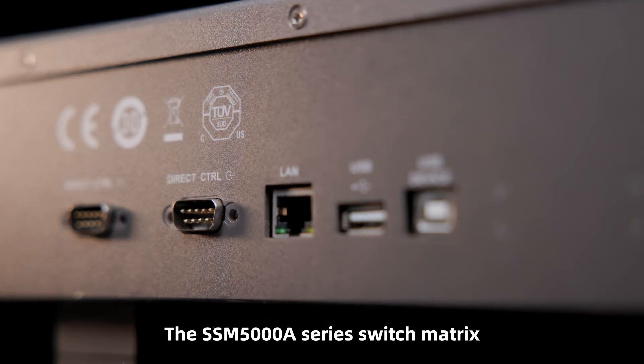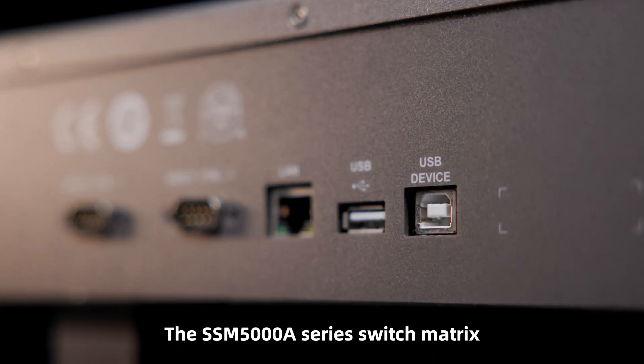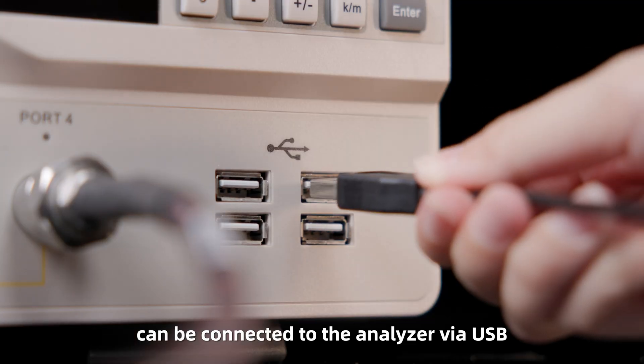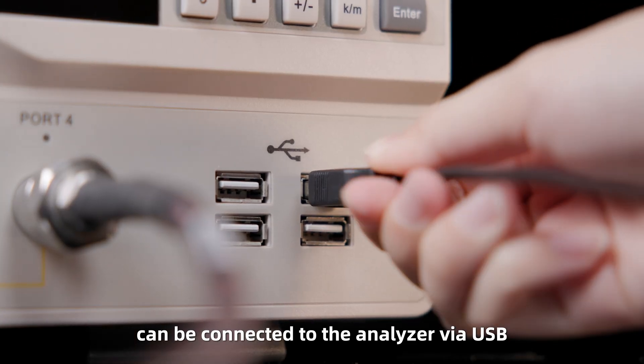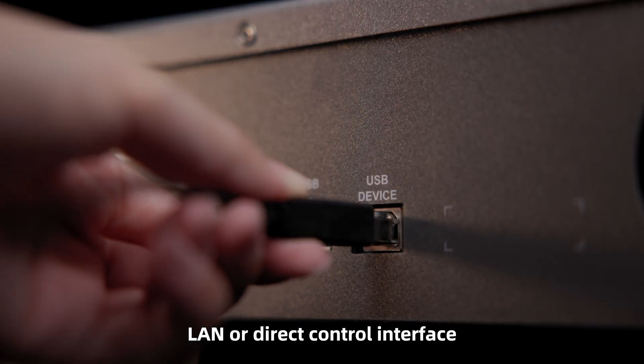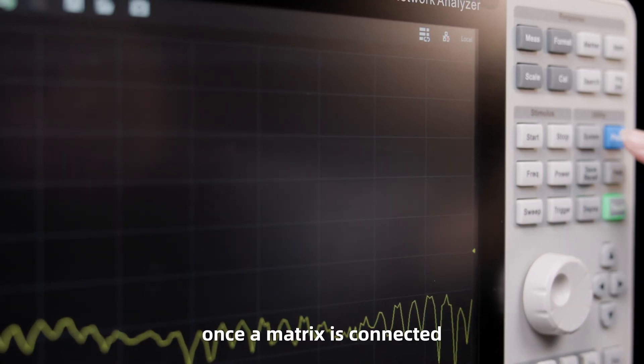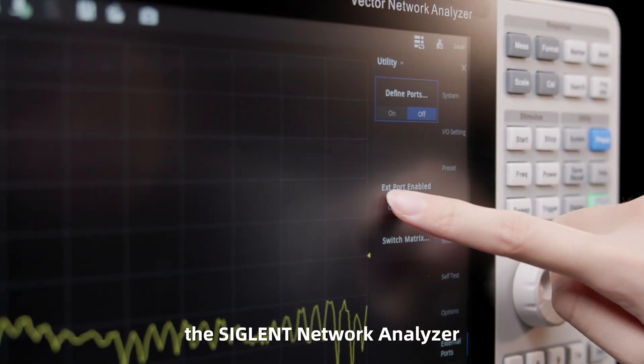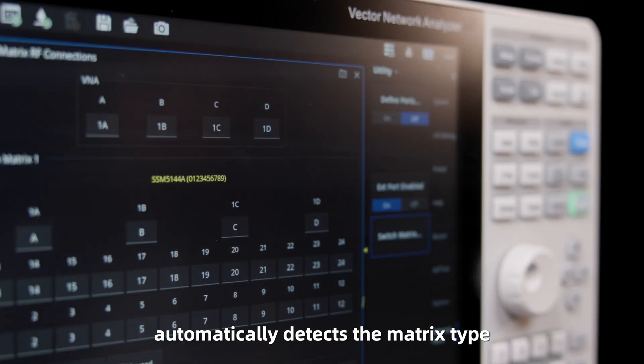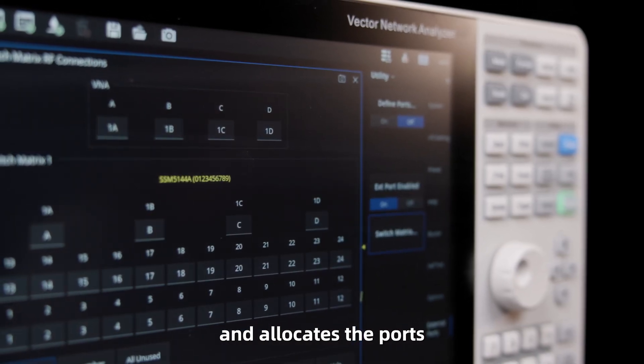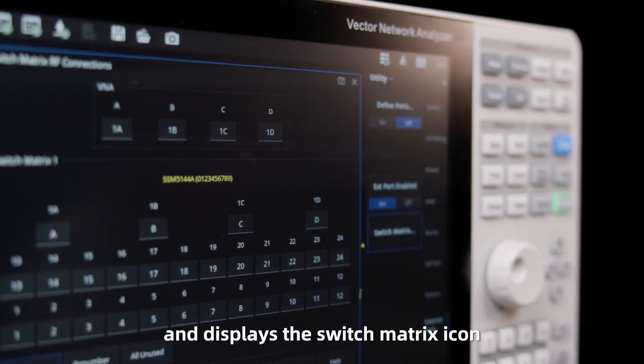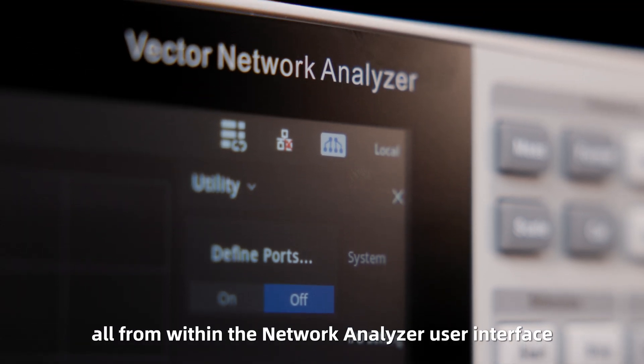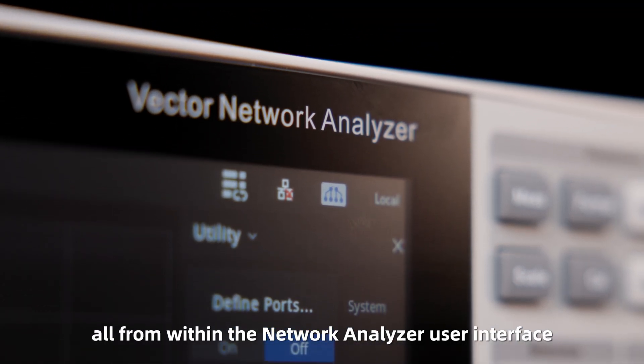The SSM5000A series switch matrix can be connected to the analyzer via USB, LAN, or a direct control interface. Once a matrix is connected, the Siglent network analyzer automatically detects the matrix type, allocates the ports, and displays the switch matrix icon, all from within the network analyzer user interface.